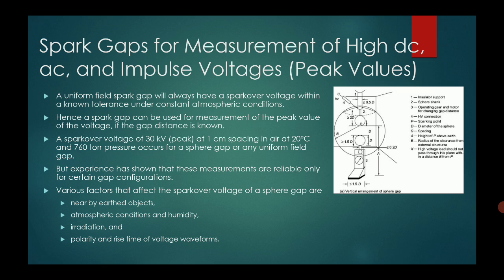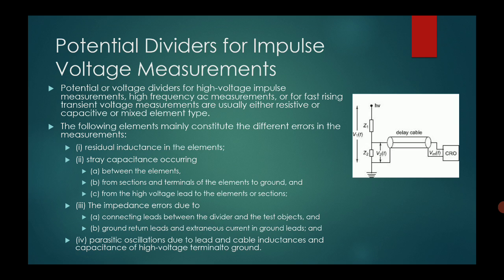But experience has shown that these measurements are reliable only for certain gap conditions. The spark over voltage at different temperature and pressure depends on several factors. The factors that affect the spark over voltage of a sphere gap are how near an earthed object is, the atmospheric condition and humidity, irradiation, and the polarity and rise time of the voltage waveform. All these factors affect the spark gap voltage measurement.